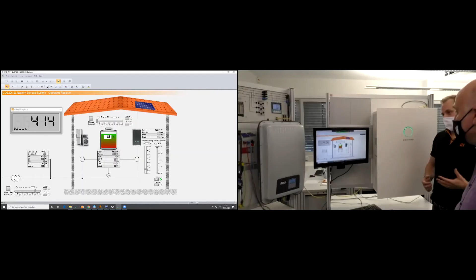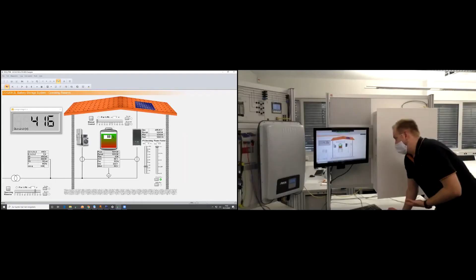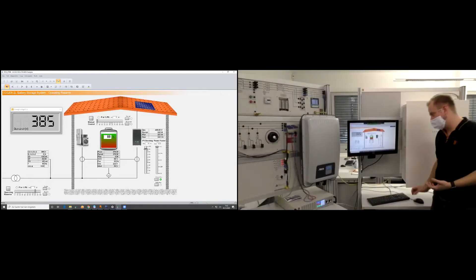One thing we can do is derate the PV inverter. So a provider can add a limitation to your PV system to hold the grid stable. So if I add now 90%, there's a limitation - only 10% of its possible power will be fed to the system. And we can see it directly at the solar panel: the MPP point is not at the top, it's lower, because it cannot provide power to the grid.